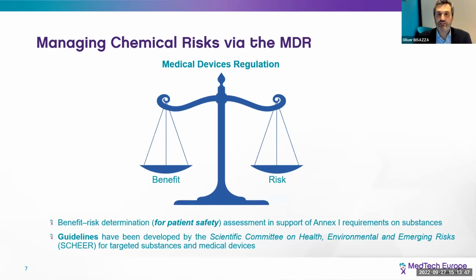So if there are chemical substances, for instance, in a medical device, which may pose particular risks to the patient or user, that's very serious. And we would only be able to justify those chemicals' presence in the device if we show that the benefits of the device go away or go down without the chemical. So a classic example might be, I don't know, some kind of implant where a chemical is there to provide a certain level of performance, you know, durability, lightweight, resistance against breaking when it's inside the patient. If that chemical is truly essential to giving the product the performance that patients and doctors require, then potentially the chemical's presence is justified. If the chemical is not playing such a clear role and it can be removed, then it's very hard, maybe impossible, to justify why the chemical should remain in there. Okay, so we're balancing benefits and risks.